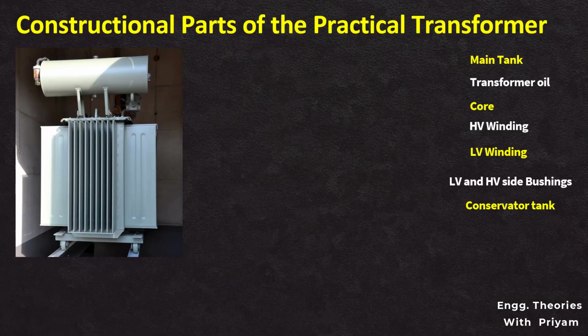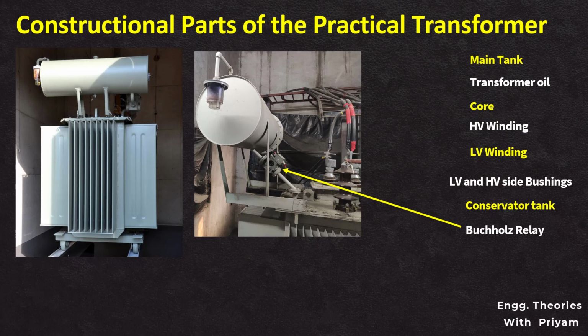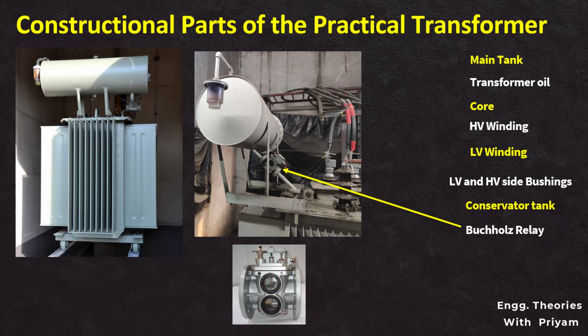The next component we want to talk about is the Buchholz relay. The Buchholz relay is the safety device typically installed in the pipework between the transformer tank and the conservator. Positioned at a strategic point, these relays serve as a protective mechanism for oil-filled transformers. The Buchholz relays function by detecting abnormal conditions within the transformer, such as the presence of gas or a rapid increase in the oil flow. In the event of a fault, such as an internal short circuit or overheating, gases are produced and accumulate in the relay. This triggers the Buchholz relay, which in turn activates an alarm or initiates the tripping of the transformer to prevent further damage.